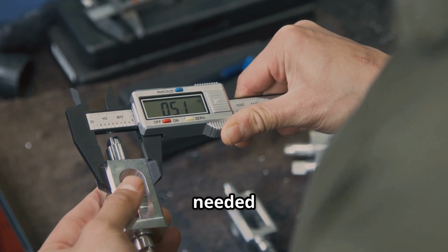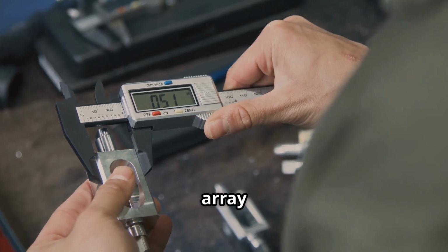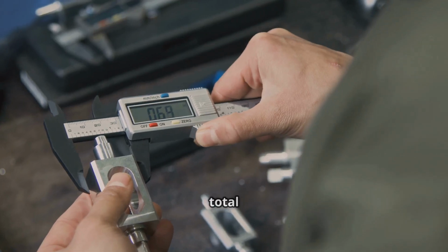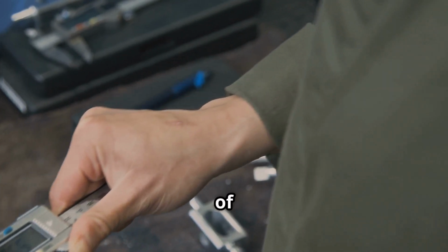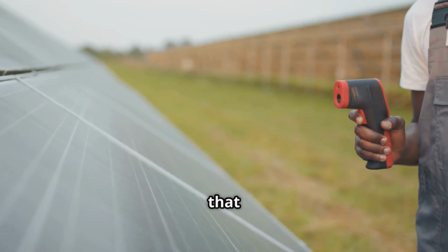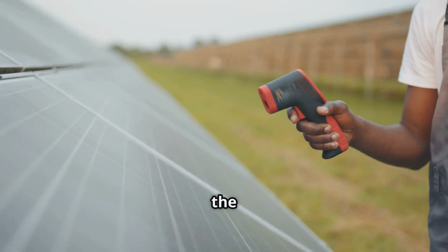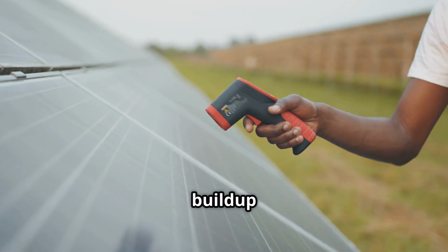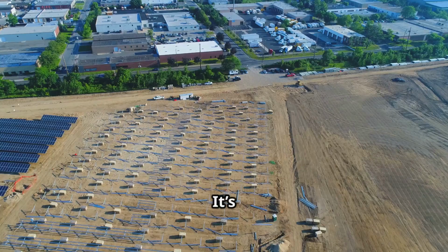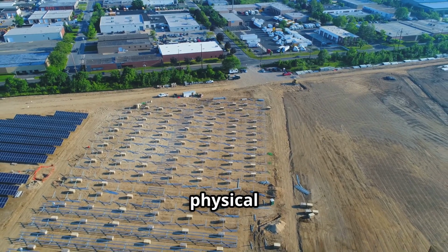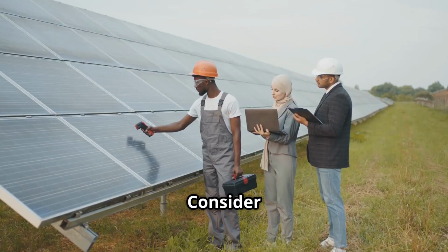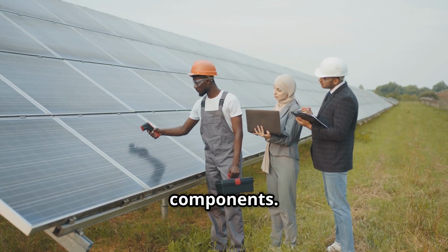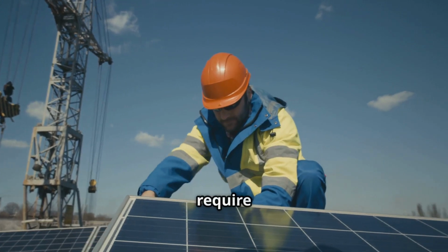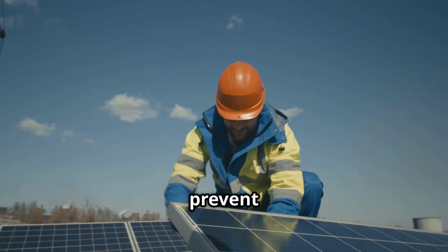calculate the wire gauge needed for each segment of your array by taking into account the total current and the length of the run. This ensures that your wiring will efficiently carry the current without excessive heat buildup or voltage loss. It's also vital to plan the physical layout of your wiring. Consider the distances between the components. Longer cable runs may require thicker wires to prevent voltage drop.